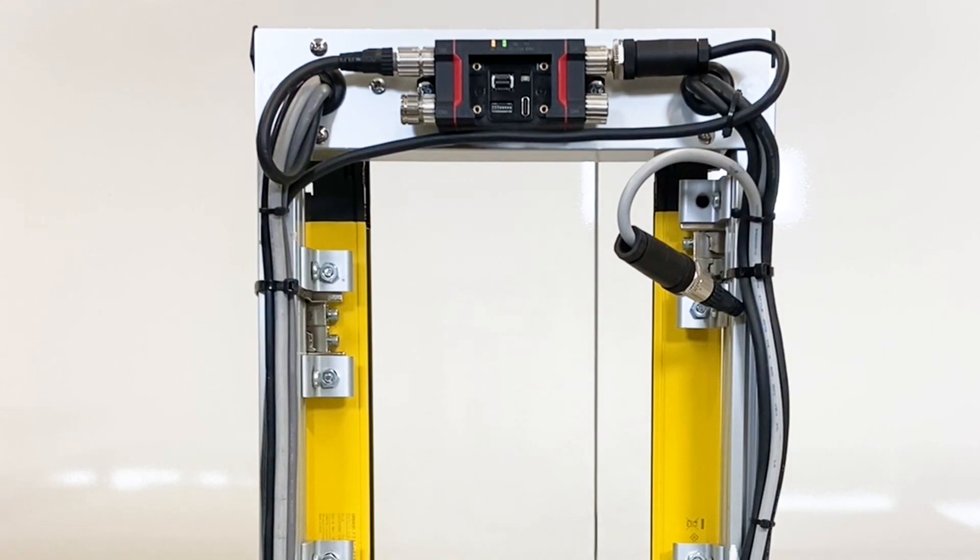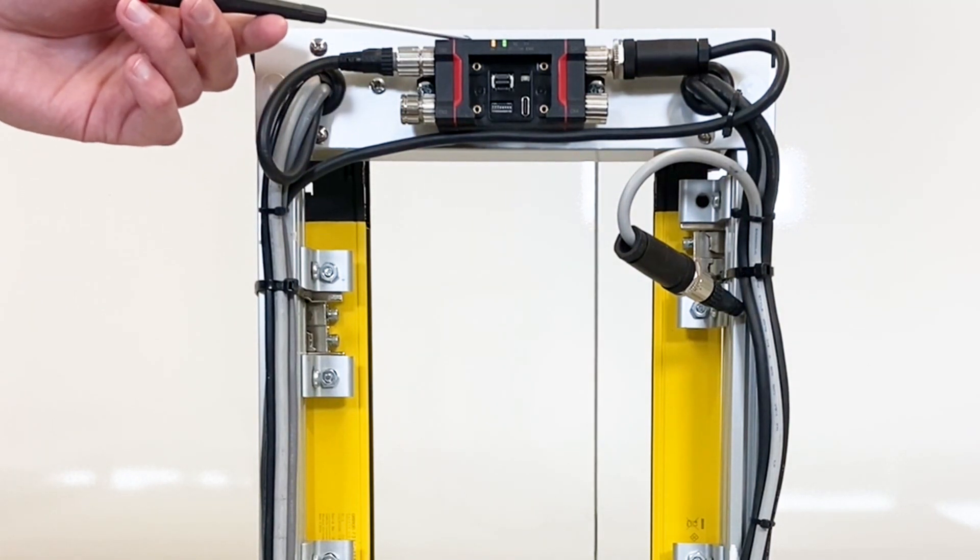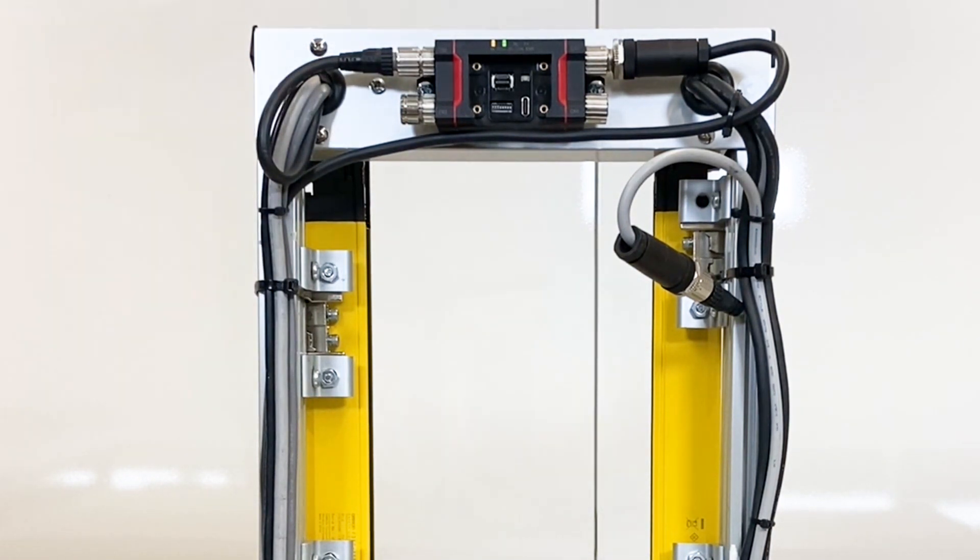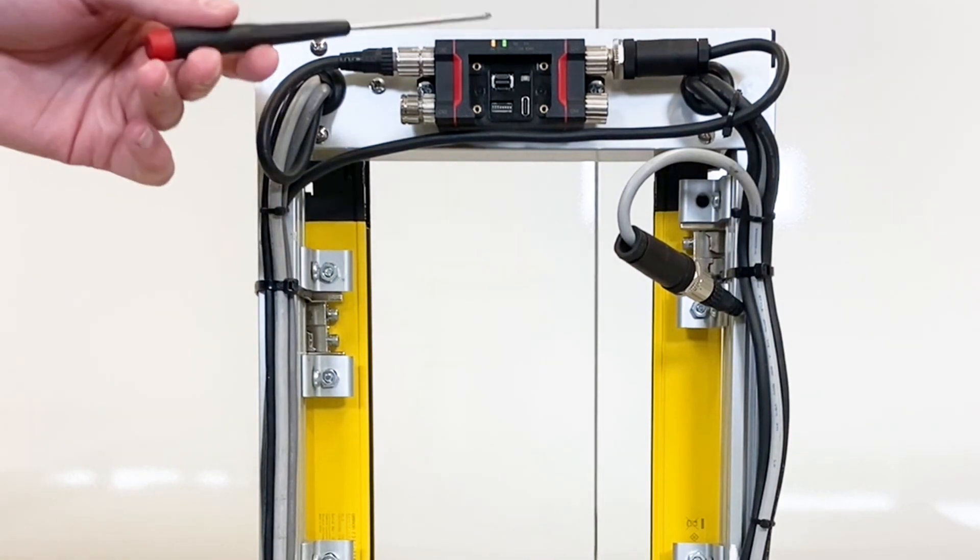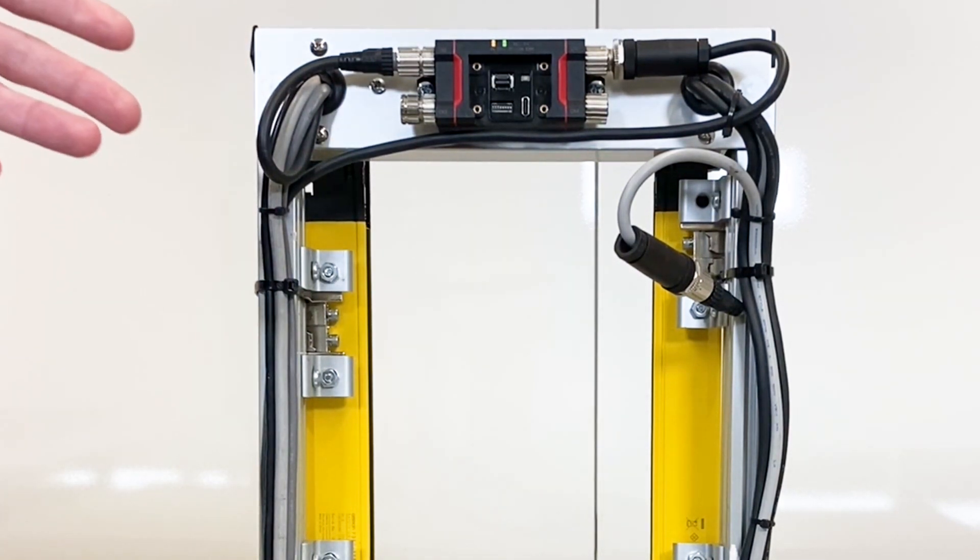As you can see, you can check the indicator lights on top to make sure that the EDM was properly downloaded to your safety light curtain. So green and orange means that everything was downloaded properly.